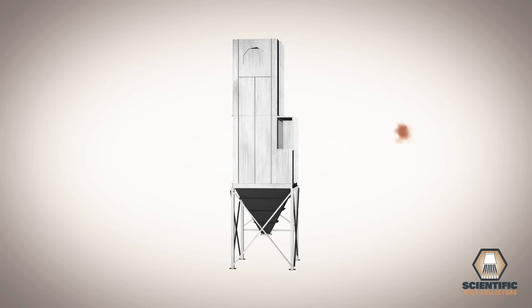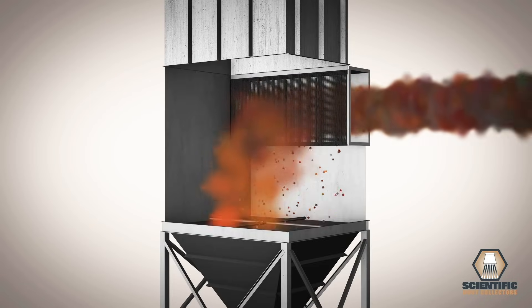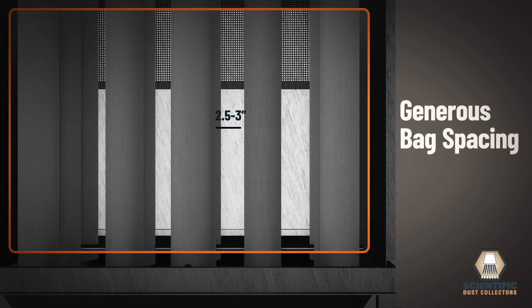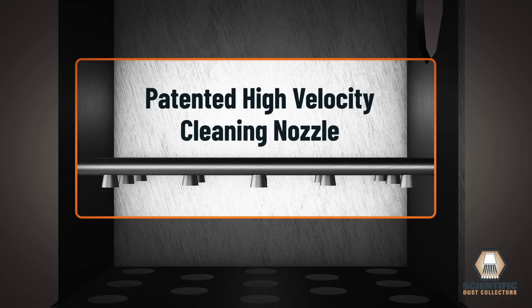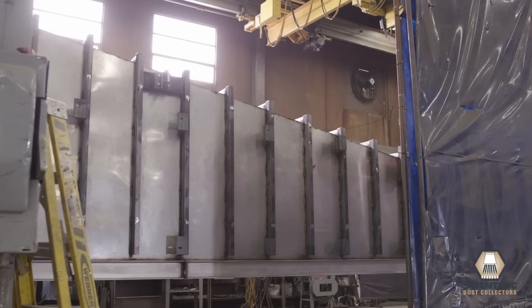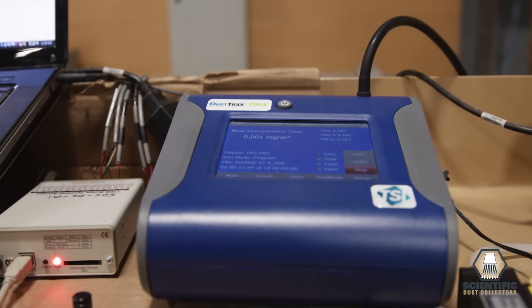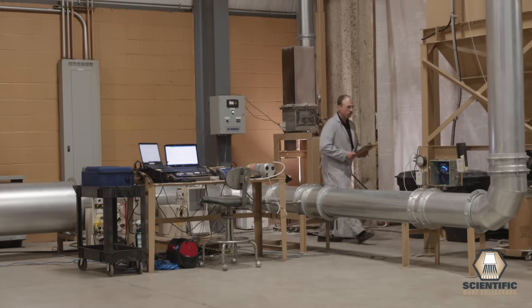We use a high side baffled inlet that creates a downward airflow and allows larger particles to drop out. We also space bags more widely to reduce velocity between the filters and use our supersonic cleaning nozzle to eliminate airflow-restricting venturi. These special features allow our baghouses to operate with fewer filters at a higher air-to-cloth ratio than all our competitors.